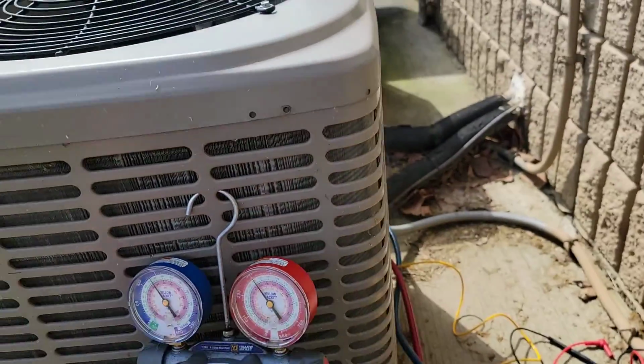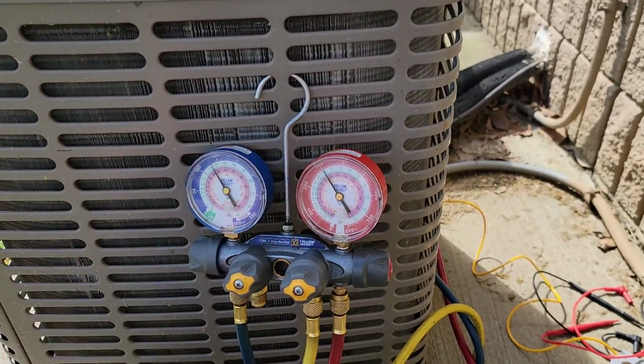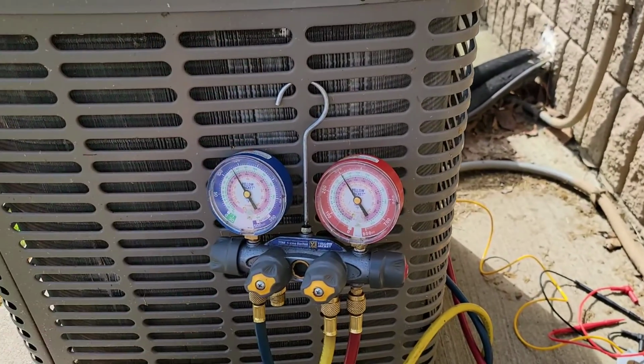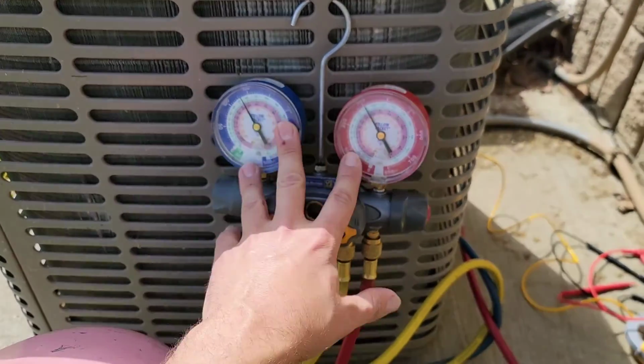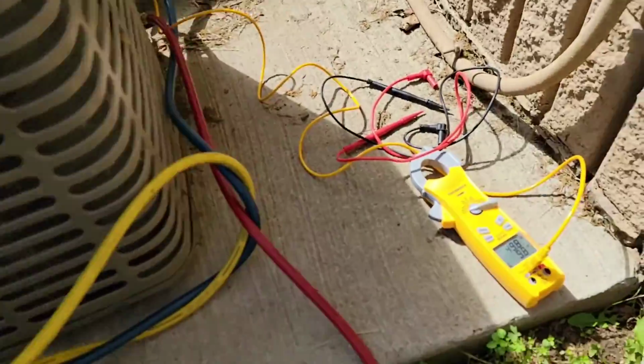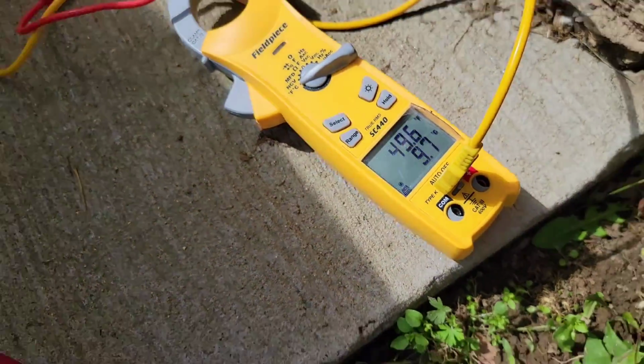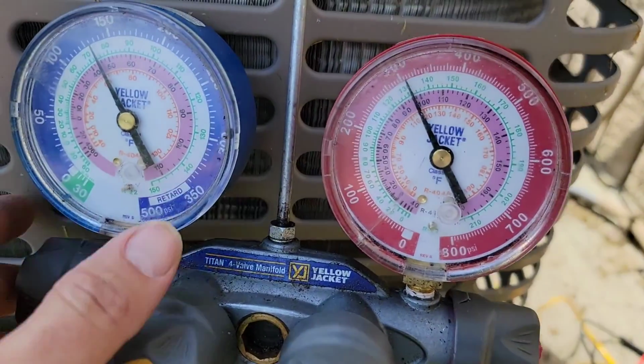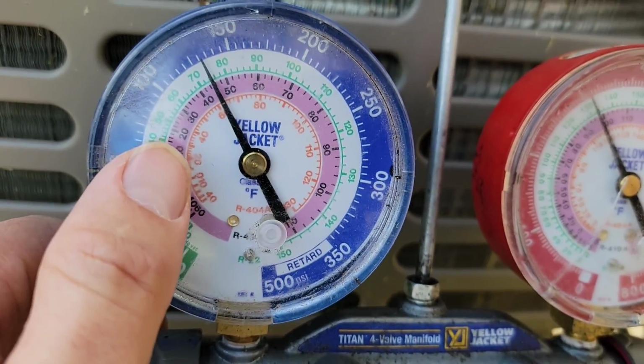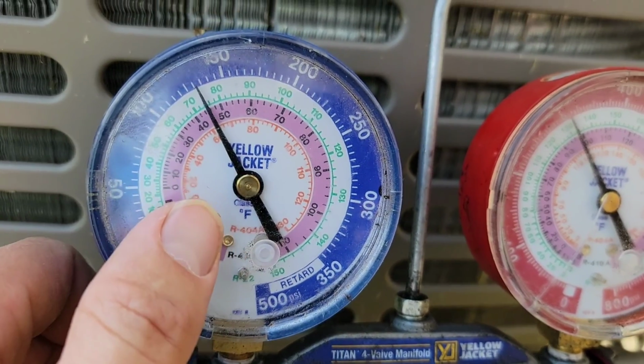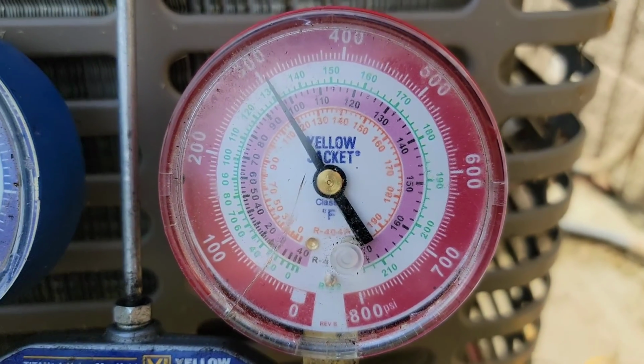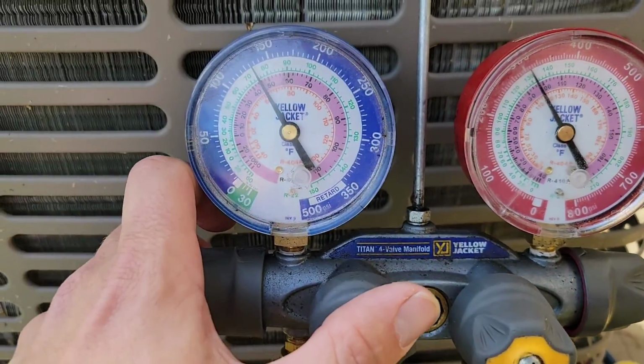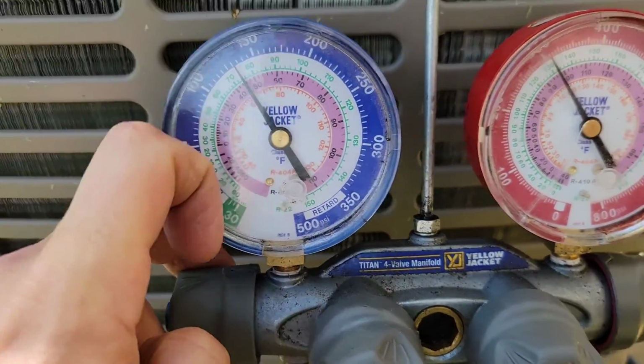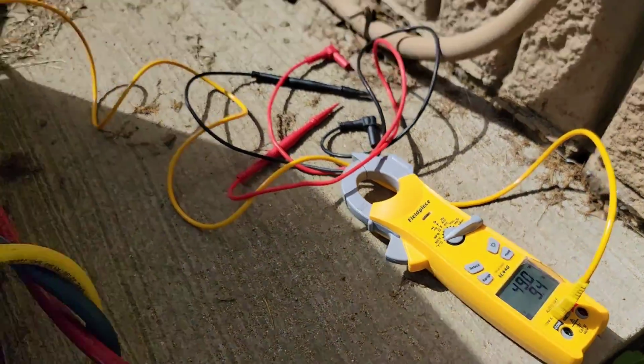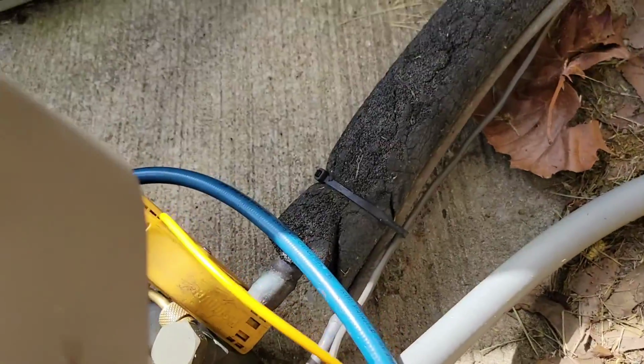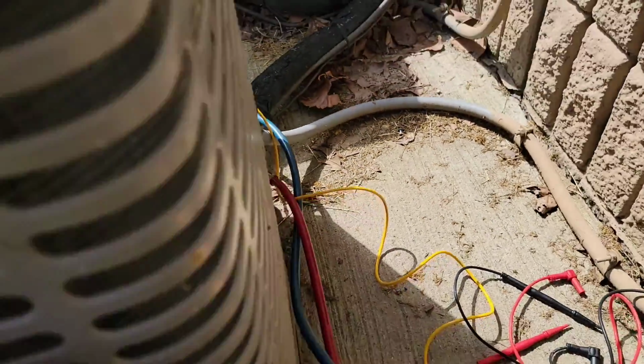You'll check factory charge, and you'll get so good at this, you'll be like, it's halfway. You know, there's only half the refrigerant in the system. You'll know just judging off the standing pressure when you put the gauges on. Look at this, 49 degrees. We dropped that temperature quick. And now our suction pressure is 130. So we moved up about 5 or 6 psi, but it was enough. See, our saturation temperature is 45. So that was enough to start making this line really cold, start sweating. Sometimes it doesn't take much.